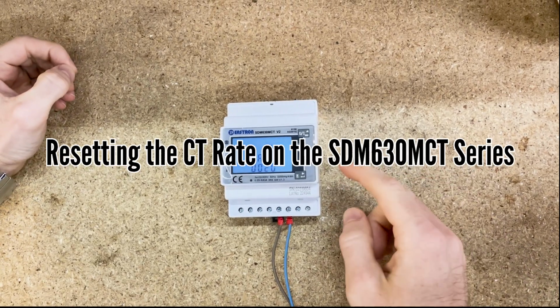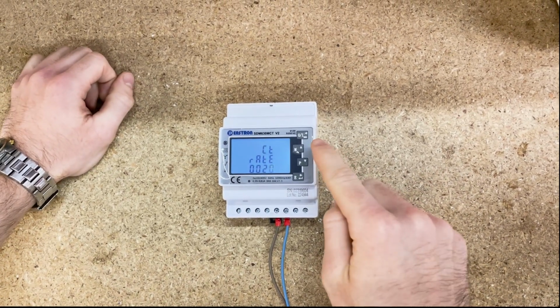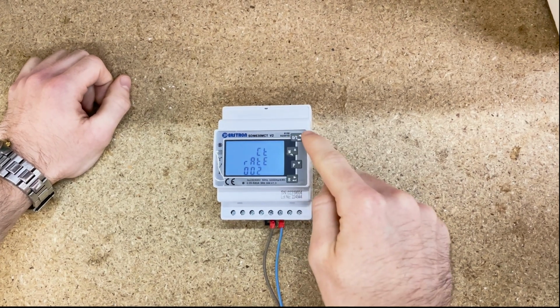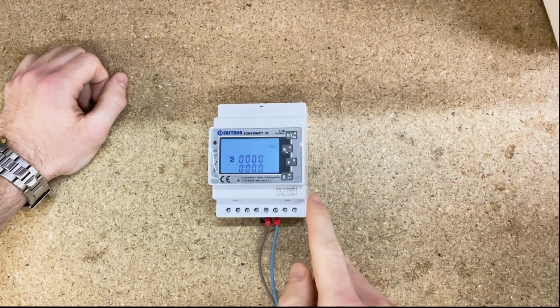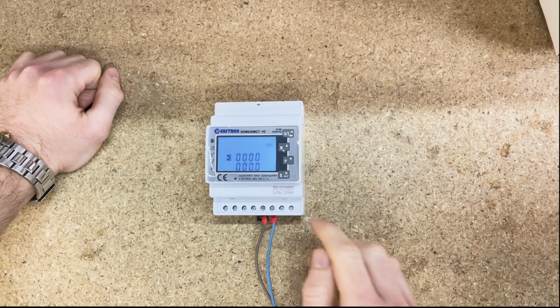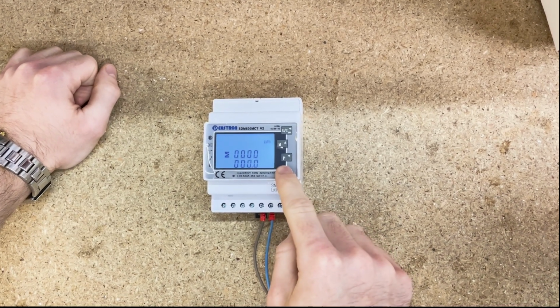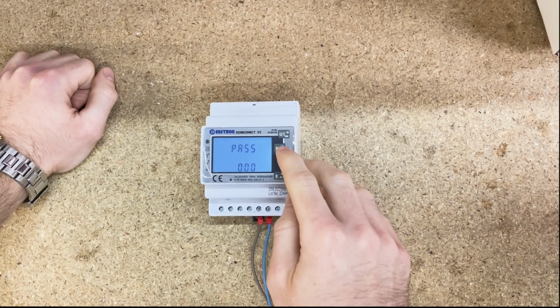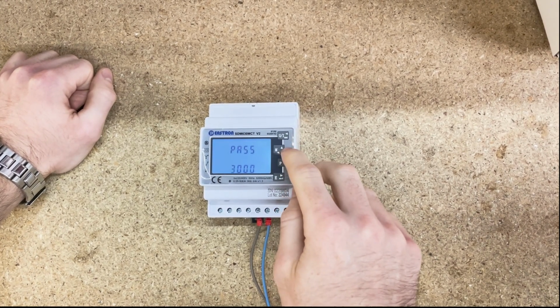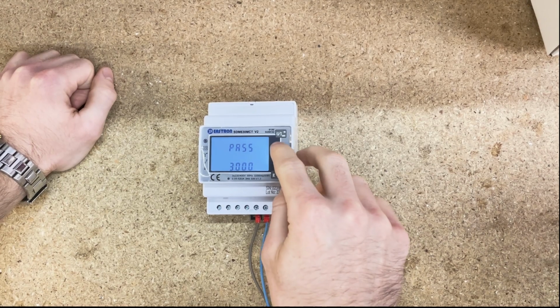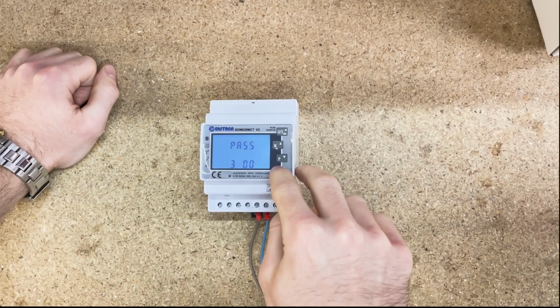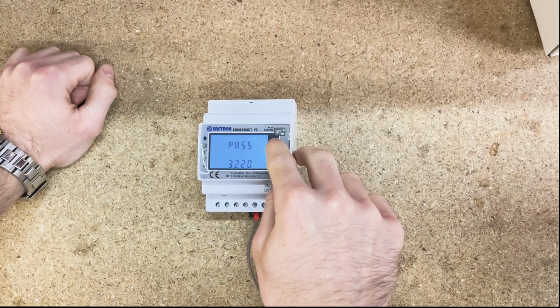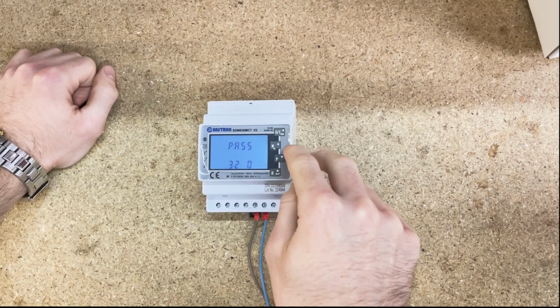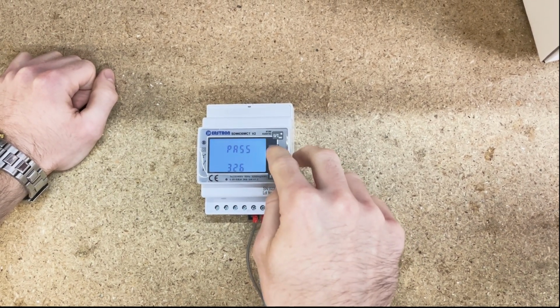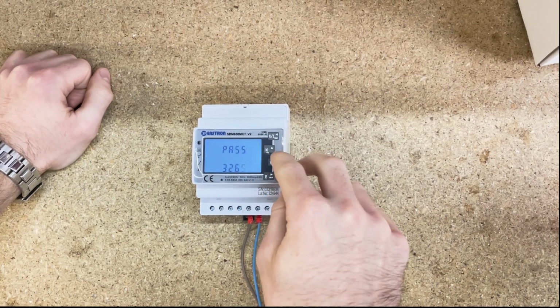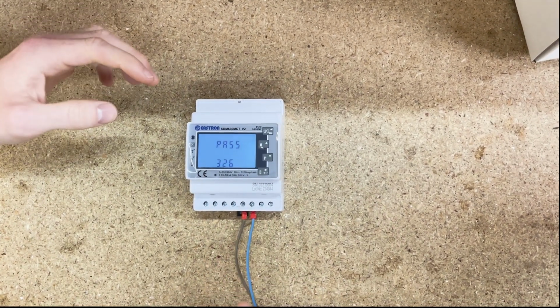So to come out of the settings menu on the meter, you have to press the escape button at the top there. Press that a couple of times, and then we're back into the parameters now. So if you press and hold the E button, and then use the password 3, 2, 6, 5. So now we put the 3265 in.